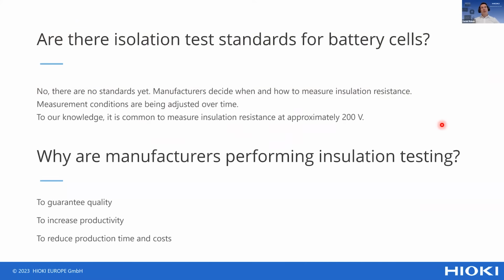And now let's look a little bit closer at how we see it in the market when manufacturers are doing this test and how they are doing their test. At the moment, there is no standard available. So every manufacturer is doing their testing a little bit differently. That means they might do it at different times, and they also apply different voltage levels. To our knowledge, it's approximately 200 volts which are being applied.